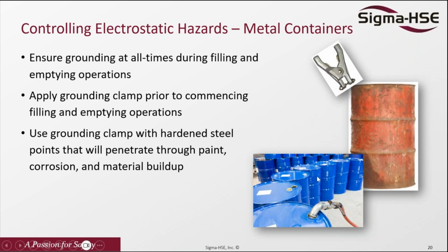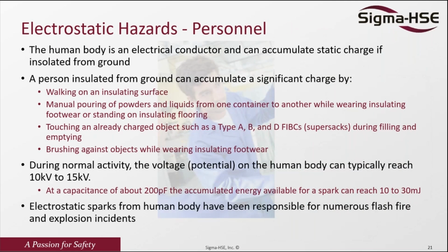Anytime you are handling any kind of flammable solvent, you need to ensure that they are properly grounded. And sometimes we might assume connecting to the clamp automatically means it is grounded. No, sometimes you need to ensure the metal-to-metal contact is complete. And actually, you can also use a mega ohmmeter to check the resistance, whether the material is actually bonded or grounded.